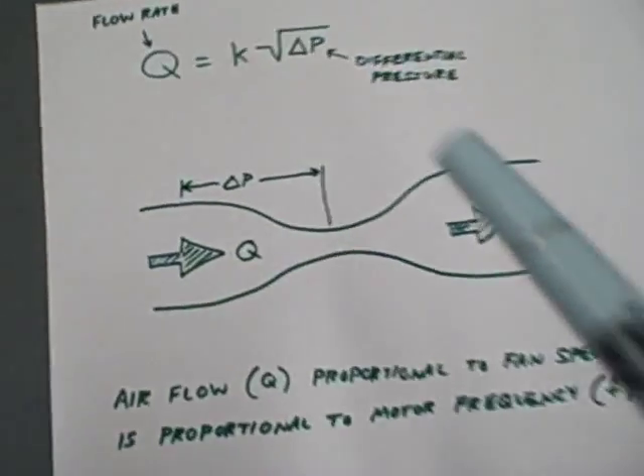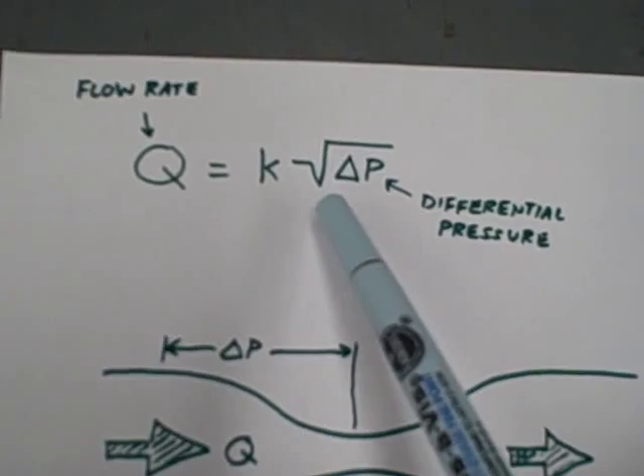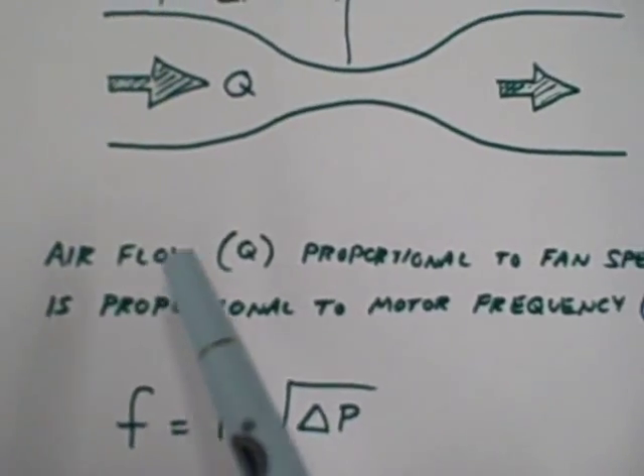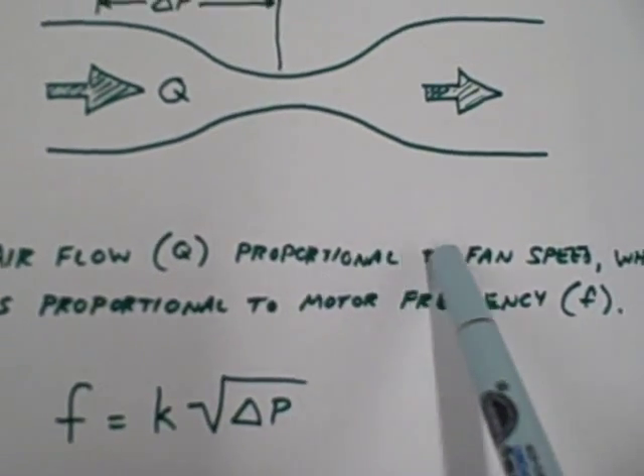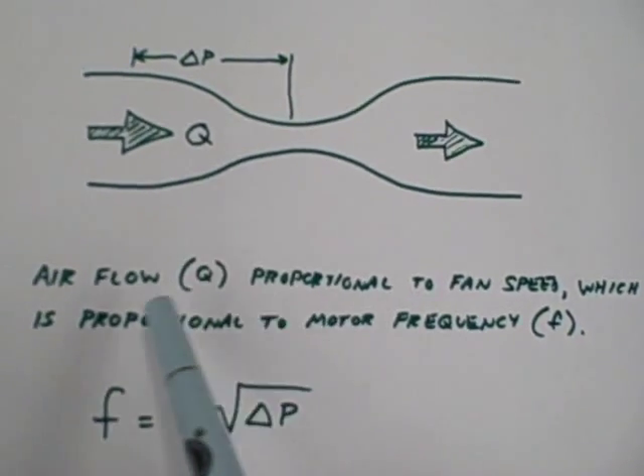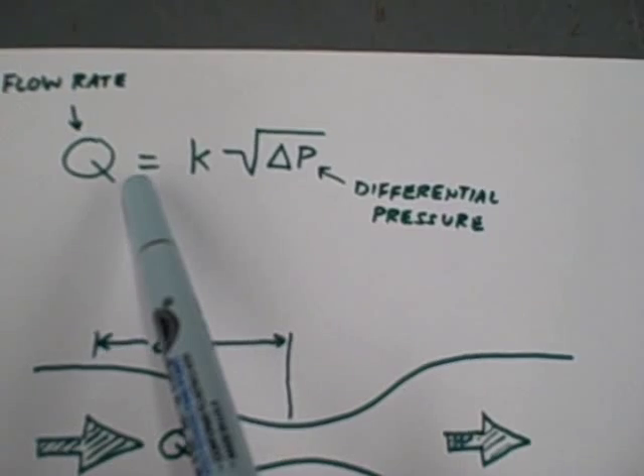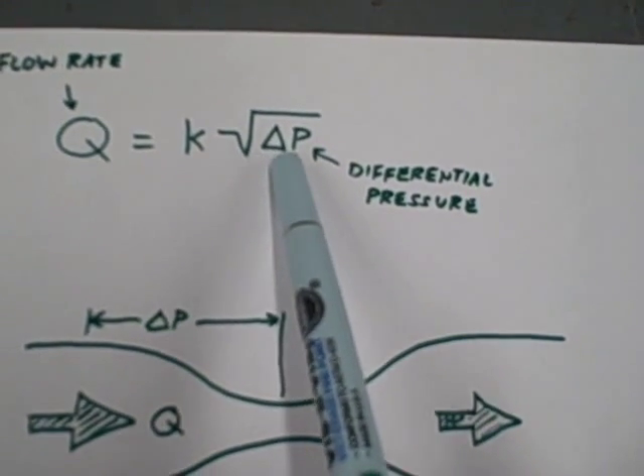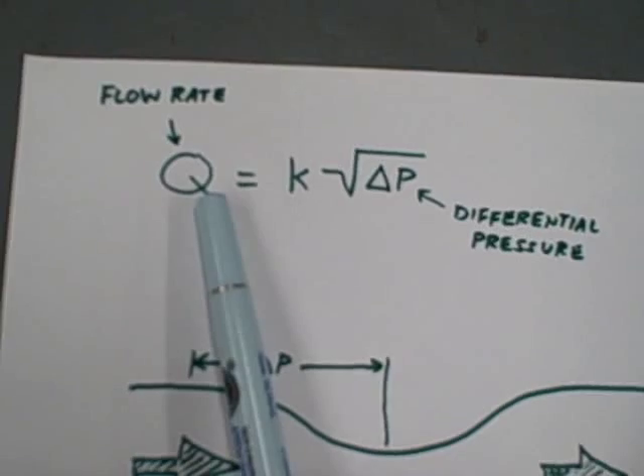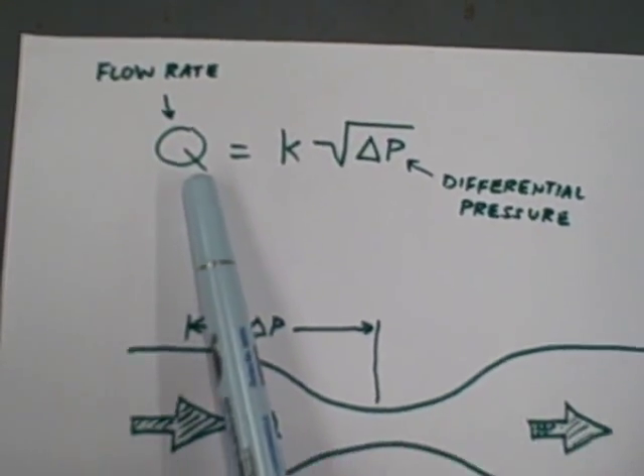As we see from the equation here, Q is equal to K times the square root of delta P. Air flow, Q, is proportional to the fan speed, which is proportional to motor frequency. We see here air flow is equal to K times the square root of differential pressure, and that air flow is typically measured in cubic feet per minute or some other volumetric unit.